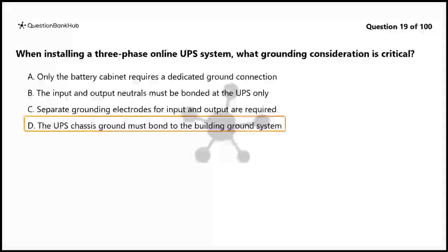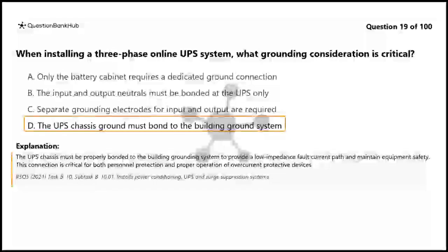The correct answer is D. The UPS chassis ground must bond to the building ground system. The UPS chassis must be properly bonded to the building grounding system to provide a low-impedance fault current path and maintain equipment safety. This connection is critical for both personnel protection and proper operation of overcurrent protective devices.